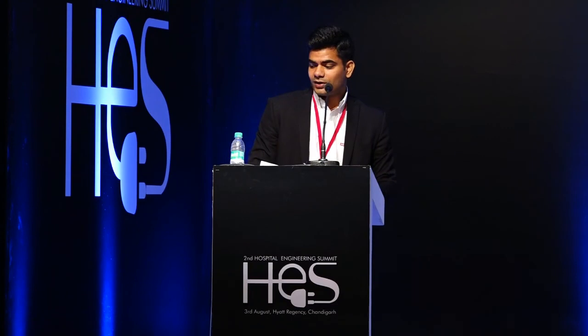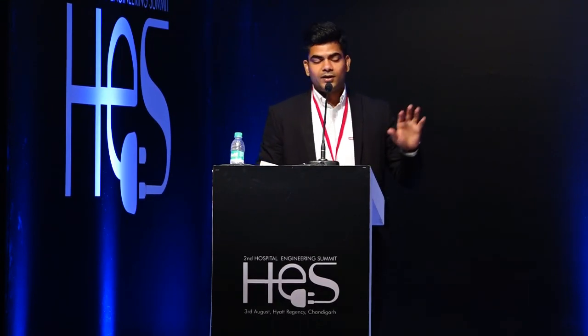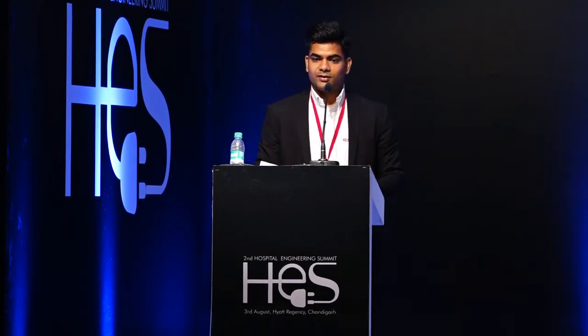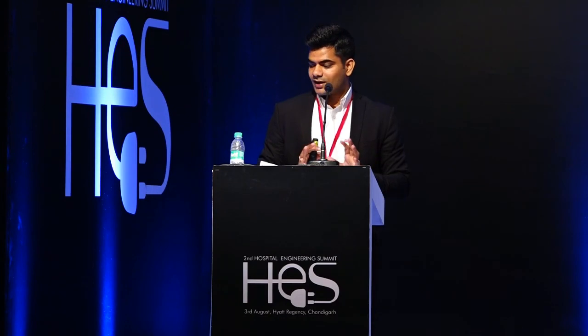Just wanted to focus on this, because I used to design sprinkler systems before and do the hydraulic calculations - a lot of calculation. But the crux is that a sprinkler system is designed for a particular number of sprinklers operating at one time. The moment one or two more sprinklers open - for example, if it's designed for 10 sprinklers, the moment the 11th sprinkler opens, your entire system design gets overtaxed.